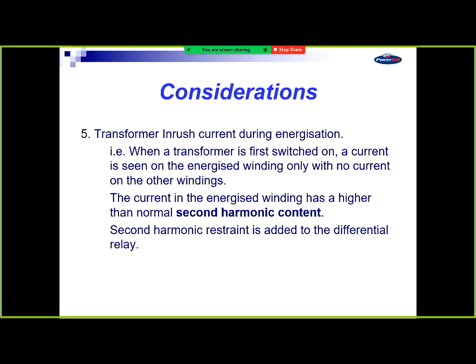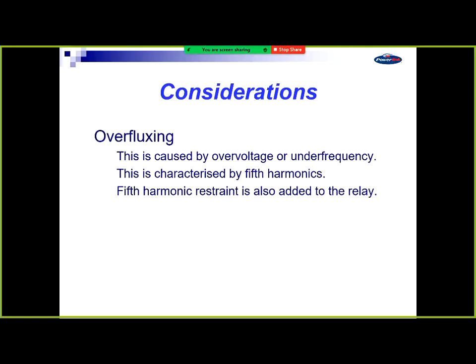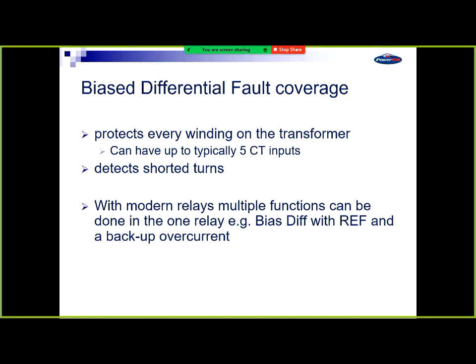Transformer inrush, that's another thing you need to be concerned about. It actually has a high level of second harmonics in it, so we put a second harmonic restraint in there to prevent tripping on inrush. Overfluxing is caused by overvoltages and under frequency. This has a lot of fifth harmonic. We put a fifth harmonic restraint in there. You've got to protect for overvoltage and under frequency, but that's a network thing. That's not a transformer fault thing. So the operators or some other protection has got to take care of that, not your transformer protection.